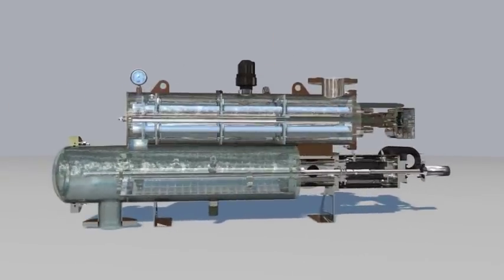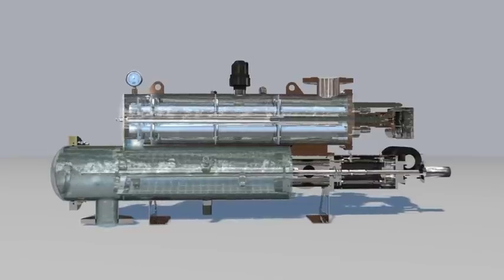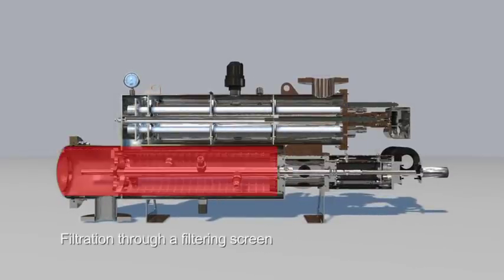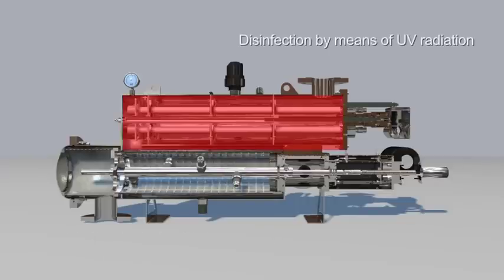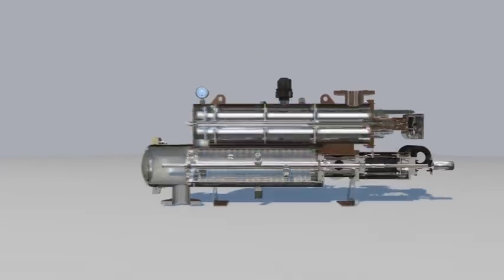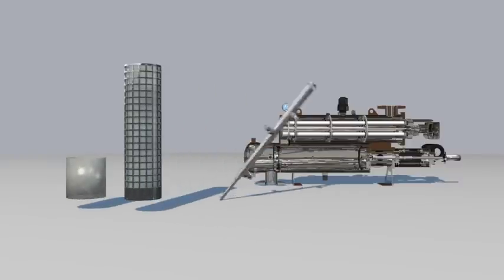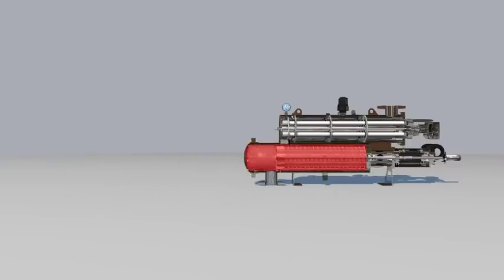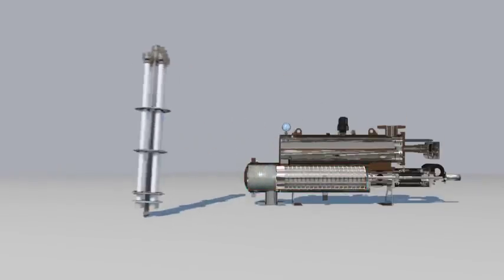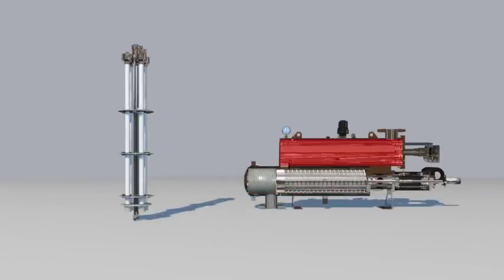The flow of liquid through the machine is subjected to two very separate processes. First, it is filtered through a filtering screen before then undergoing disinfection via ultraviolet radiation. The pre-filtration, filtration and backwashing chambers are all related to the first process, while the disinfection chamber is related to the second.